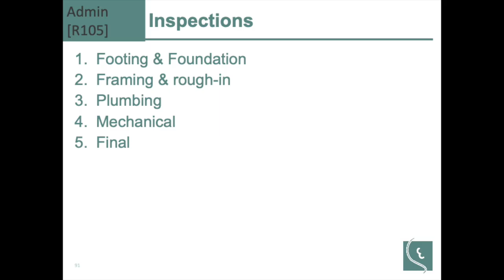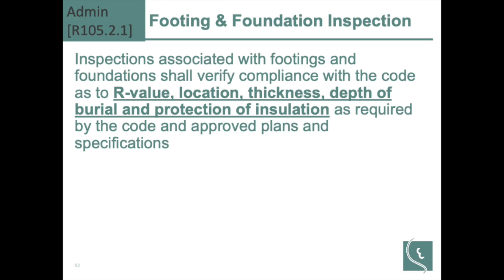So here, touching on those, what is it that we're having to look for? Obviously, footing and foundation, we're looking at our insulation and thickness. Did you actually install what you said you would put in there? I know that never happens, that they specify 2-inch insulation and 1.5 inches goes on. Framing and rough-in, again looking at our insulation, our windows, and our air leakage controls. Our air barrier should be in here at this point, because that's part of our thermal envelope, is that air barrier.